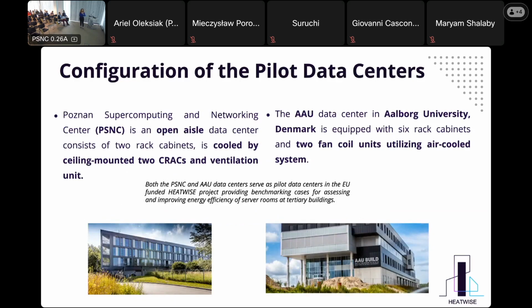We have two pilot data centers within the CFD efforts we made. The first is the Poznan Supercomputing and Networking Center. Its layout is an open-aisle data center consisting of two rack cabinets, cooled by two ceiling-mounted units specially designed for rack cooling, plus a ventilation unit. The Aalborg data center at Aalborg University is a bit larger, equipped with six rack cabinets and two fan coil units utilizing an air-cooled system.